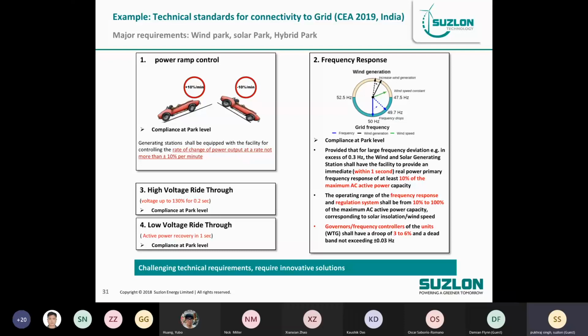Then on the other side is the frequency response, where they talk about a 10% response within 1 second. In the case of solar, it could be fast because there are no moving parts, and it can provide the power in less than 1 second. But in the case of wind, if you have to accelerate or decelerate such a huge mass of the rotor, it's quite a challenge to increase 10% power in 1 second. So that means a very large ramp rate is required here.